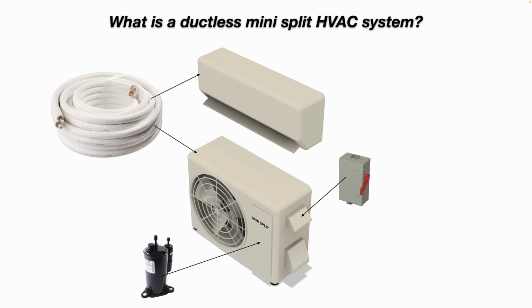And then you have your line set, which connects the outdoor condensing unit to the indoor evaporator unit. And the evaporator unit can be mounted on the wall inside the building. And again, it takes up a much smaller footprint than a traditional split system with an air handler and ductwork. And they run fairly quiet.